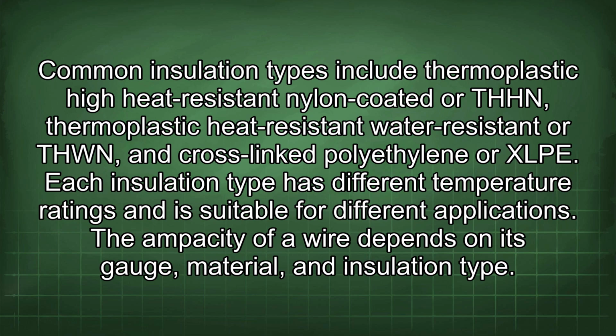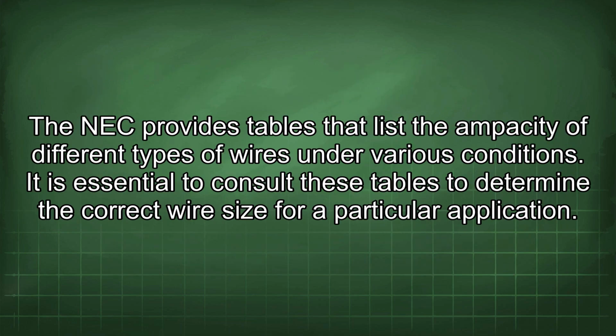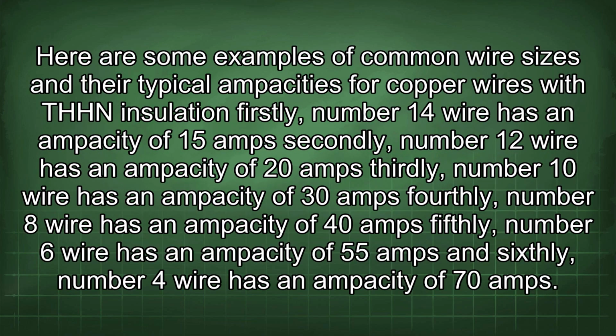The ampacity of a wire depends on its gauge, material, and insulation type. The NEC provides tables that list the ampacity of different types of wires under various conditions. It is essential to consult these tables to determine the correct wire size for a particular application. Here are some examples of common wire sizes and their typical ampacities for copper wires with THHN insulation. Firstly, number 14 wire has an ampacity of 15 amps. Secondly, number 12 wire has an ampacity of 20 amps.